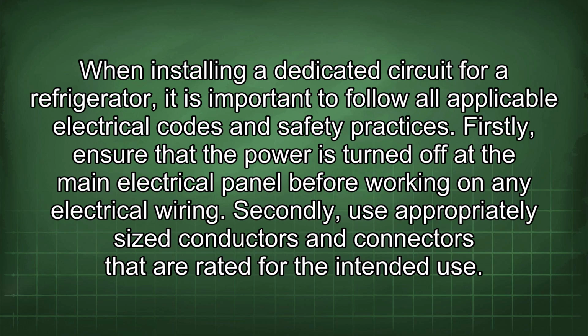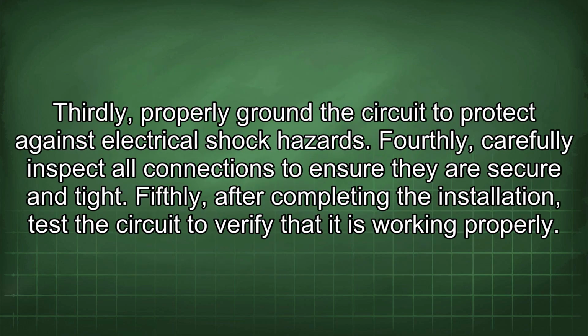When installing a dedicated circuit for a refrigerator, it is important to follow all applicable electrical codes and safety practices. Firstly, ensure that the power is turned off at the main electrical panel before working on any electrical wiring. Secondly, use appropriately sized conductors and connectors that are rated for the intended use. Thirdly, properly ground the circuit to protect against electrical shock hazards. Fourthly, carefully inspect all connections to ensure they are secure and tight. Fifthly, after completing the installation, test the circuit to verify that it is working properly.